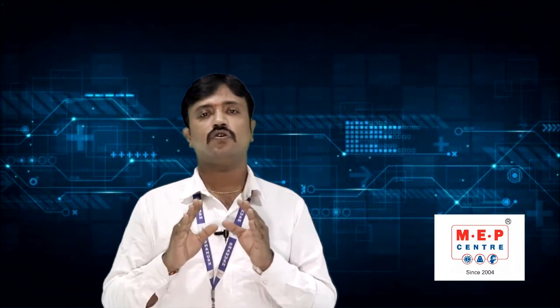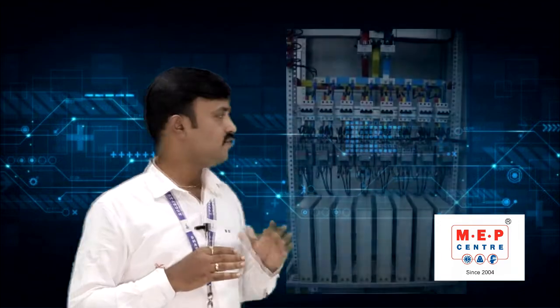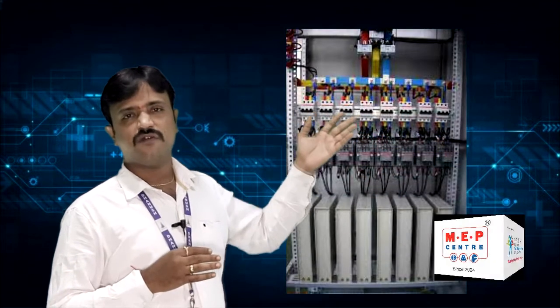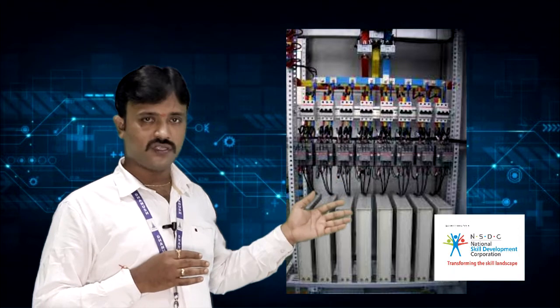But when it comes to three phase, no one is going to give a capacitor. So we need to put separate capacitor banks, or what we also call an APFC panel. That is, you can see the image. So automatic power factor correction or control panel, or we also call it capacitor banks.